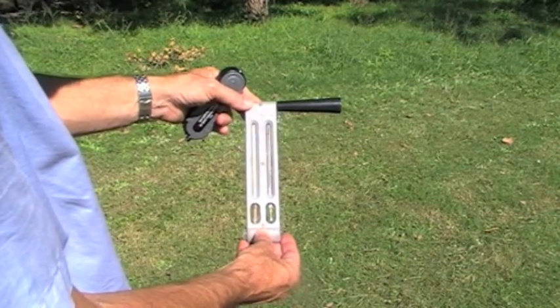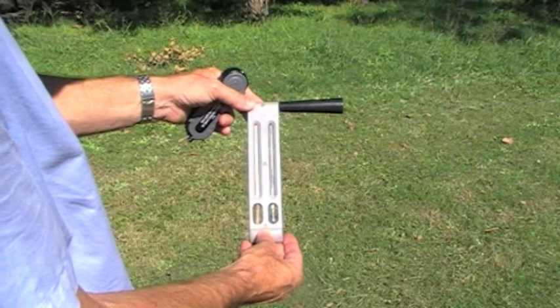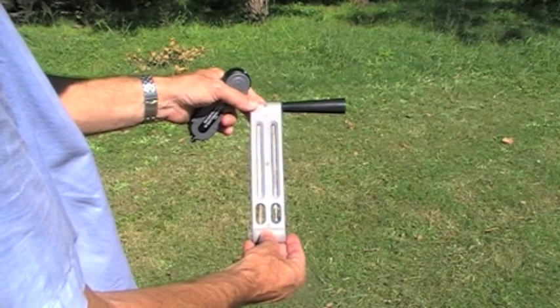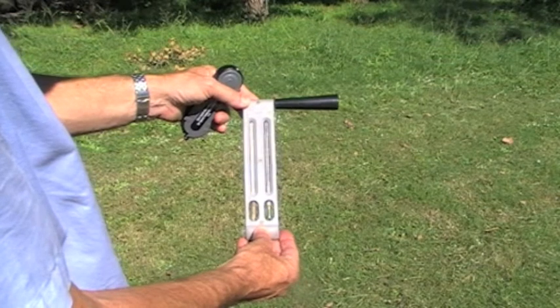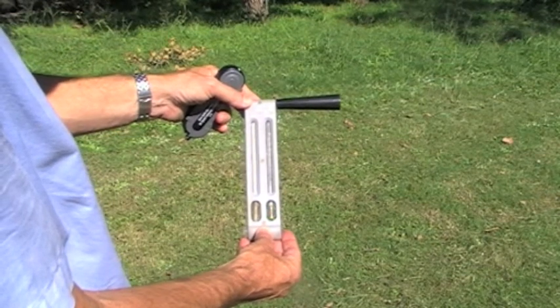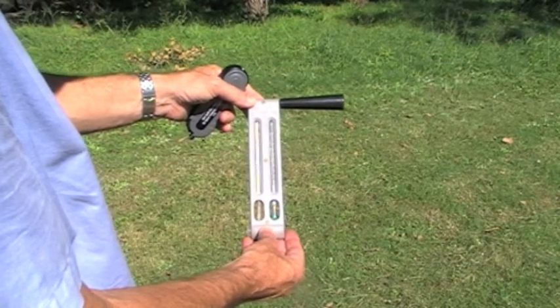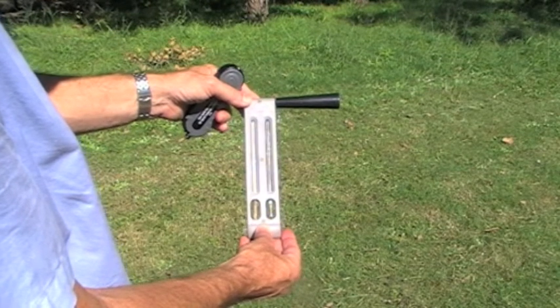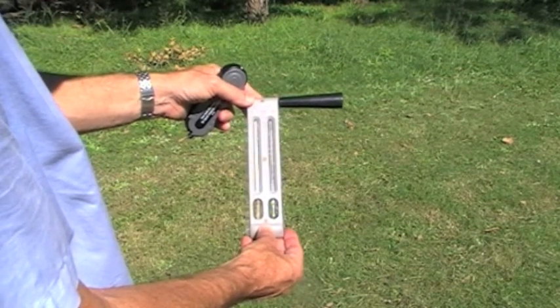The dry temperature thermometer is reading 27 degrees centigrade and the wet bulb is reading 23 degrees centigrade. That difference is a reflection of the humidity and we can actually look up the percentage of humidity in a psychrometer chart which is provided in your module.